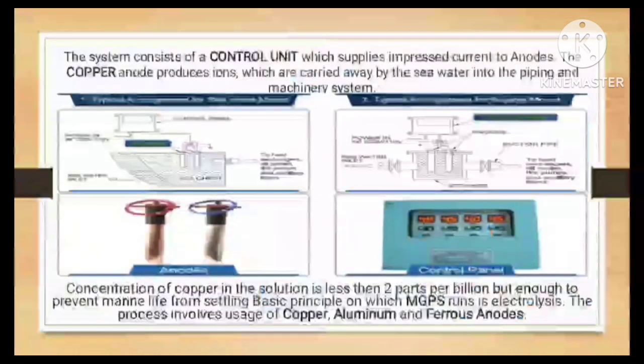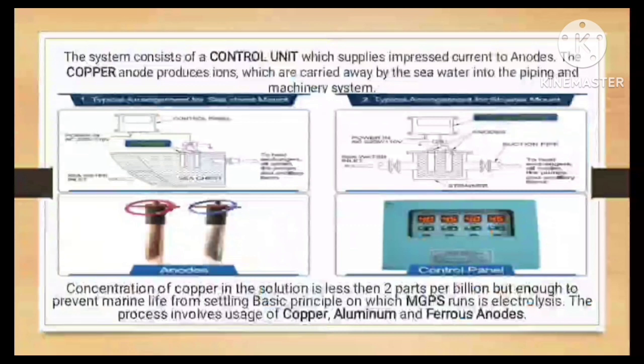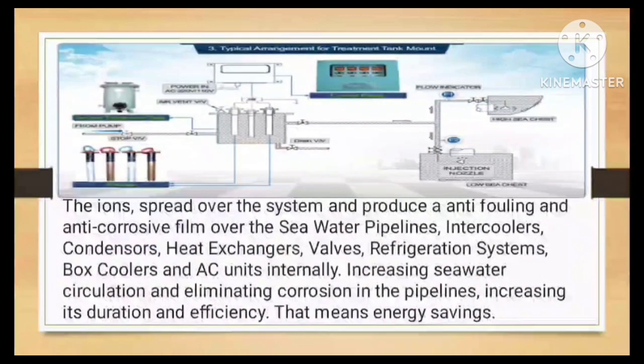The system consists of a control unit which supplies impressed current to anodes. The copper anode produces ions which are carried away by the seawater into the pipeline and machinery system. Concentration of copper in the solution is less than 2 parts per billion, but enough to prevent marine life from settling. The basic principle on which MGPS runs is electrolysis. The process involves usage of copper, aluminum and ferrous anodes.